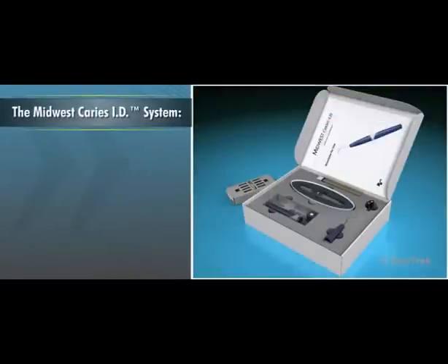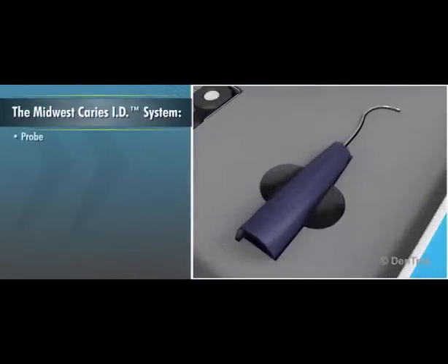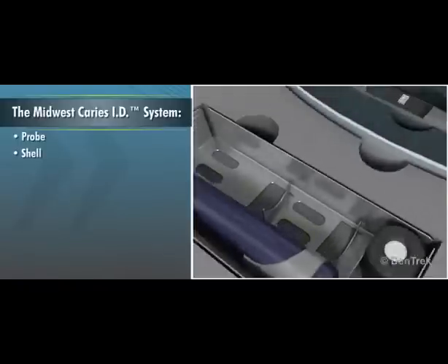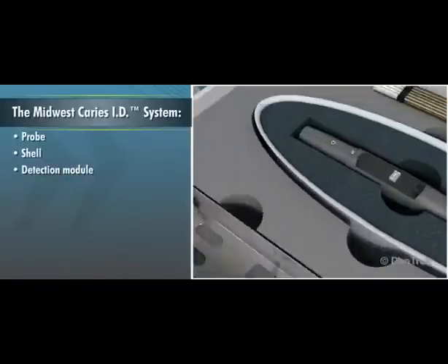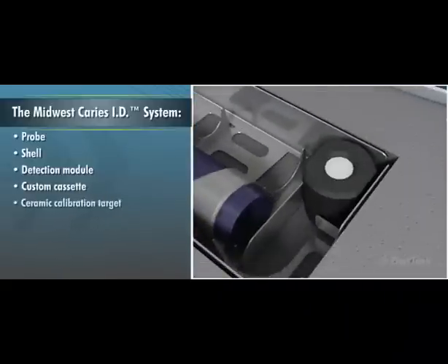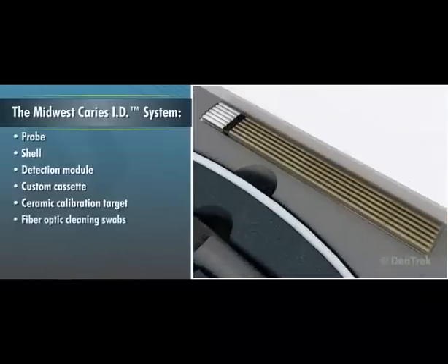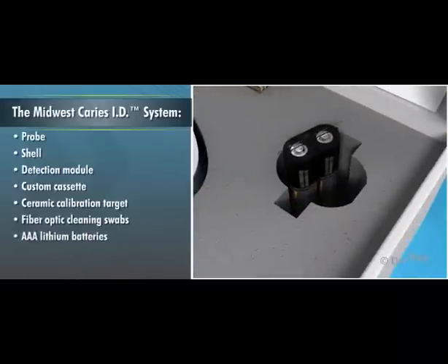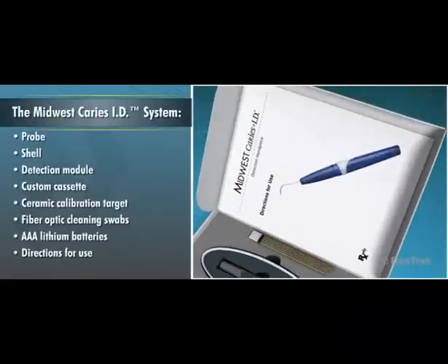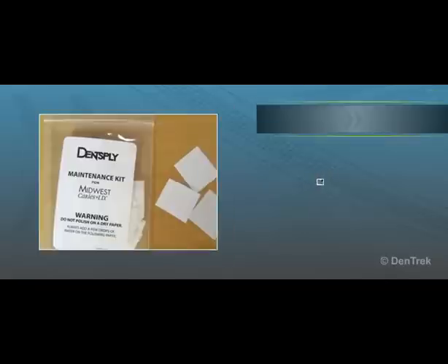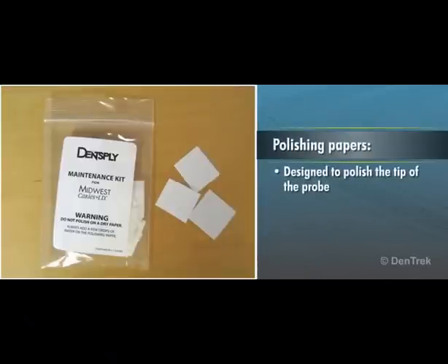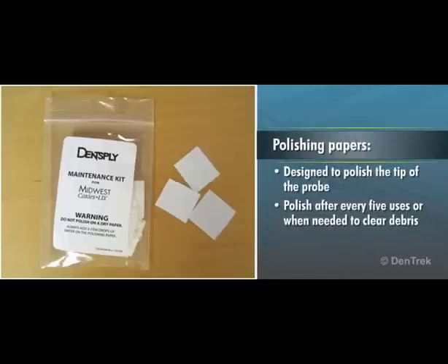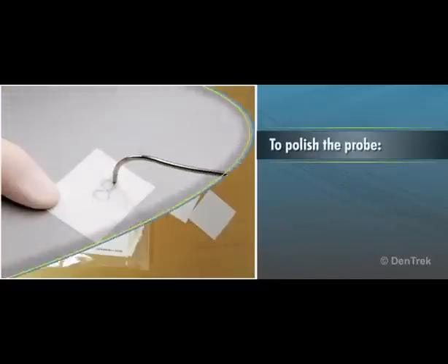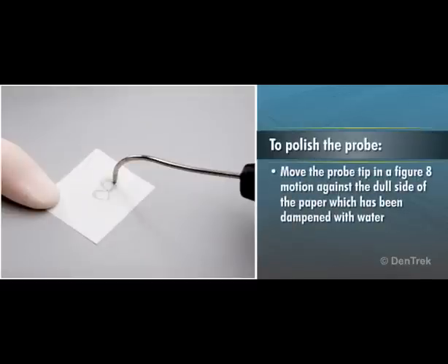The Midwest Caries ID system comes complete with the probe, shell, and detection module. It also includes a custom cassette, ceramic calibration target, fiber optic cleaning swabs, AAA lithium batteries, and directions for use. The kit also includes polishing papers designed to polish the tip of the probe. It is recommended that the probe be polished after every 5 uses or when needed to clear debris. To polish the probe, move the probe tip in a figure-8 motion against the dull side of the paper which has been dampened with water.